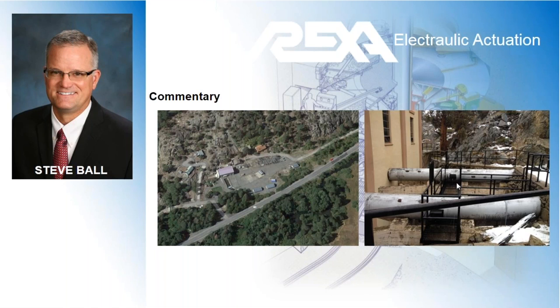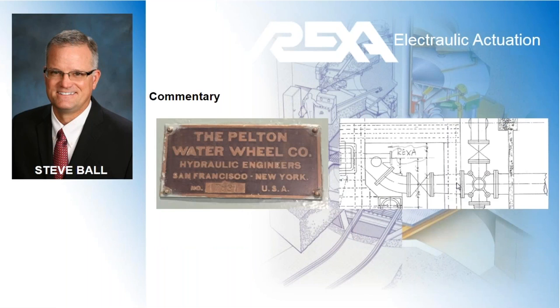What that gave us was this type of information: to close the needle, the close rate could not exceed 15 seconds per inch, which is fairly slow. But on the opening, it revealed that we could open the needle as fast as just under 3 seconds per inch, which confirmed the idea that, wow, we could do something like frequency recovery. And how could we do that?